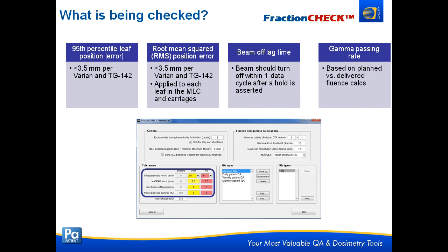When we load these files, what parameters are we actually checking? We're looking at the 95th percentile error in leaf positions — this should be less than 3.5 mm per Varian and also AAPM's TG142, though we've found we can get a better tolerance around 1 mm for a lot of treatments. We can also look at the RMS error in leaf positions, which Varian and TG142 say should be less than 3.5 mm. One unique thing about FractionCheck is it calculates beam off lag time — when the beam shuts off, the Varian log files record when the beam hold is asserted, and we can time how long it took from that assertion to when the beam was actually shut off.